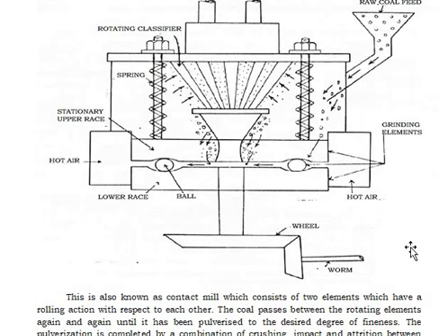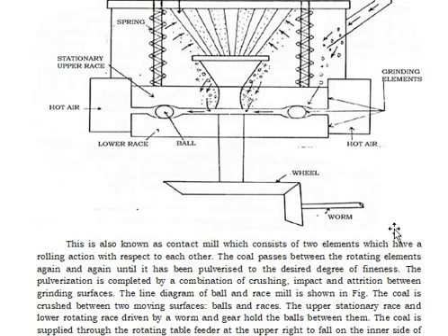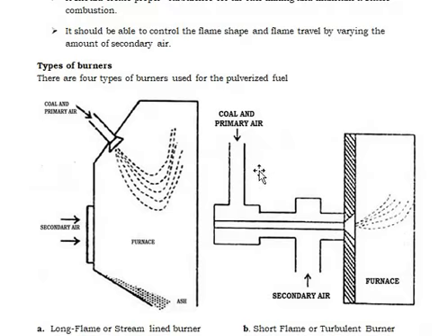This is also known as a contact mill, which consists of two elements that have a rolling action with respect to each other. The coal passes between the rotating elements again and again until it has been pulverized to the desired degree of fineness. The pulverization is completed by a combination of crushing the coal and attrition between grinding surfaces. The line diagram of ball-and-race milling is shown in the figure.